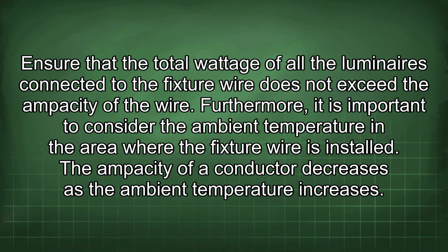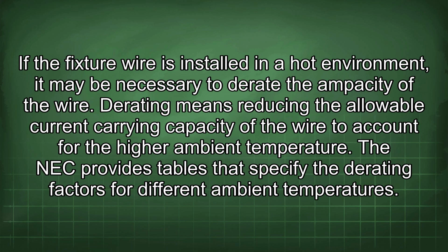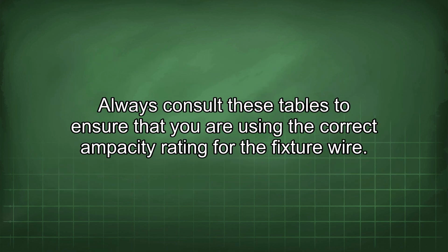Furthermore, it is important to consider the ambient temperature in the area where the fixture wire is installed. The ampacity of a conductor decreases as the ambient temperature increases. If the fixture wire is installed in a hot environment, it may be necessary to derate the ampacity of the wire. Derating means reducing the allowable current carrying capacity of the wire to account for the higher ambient temperature. The NEC provides tables that specify the derating factors for different ambient temperatures. Always consult these tables to ensure that you are using the correct ampacity rating for the fixture wire.